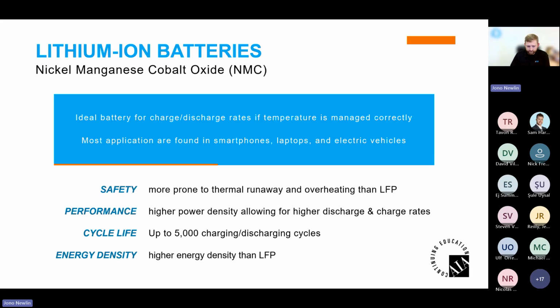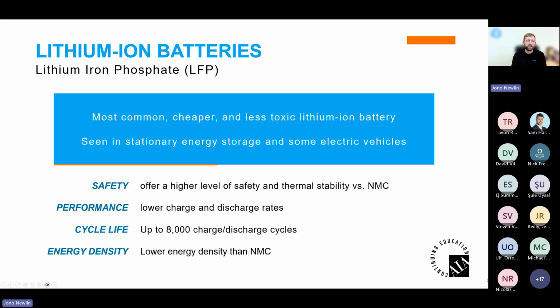These typically have up to 5,000 charging and discharging cycles. That cycle life will depend, as we get into cooling, on the environment: how often you're charging and discharging, how cold or warm it is out. Temperature drastically impacts performance, both on the safety side and on how many cycle lives you get out of these. NMC batteries are more energy dense than LFP.